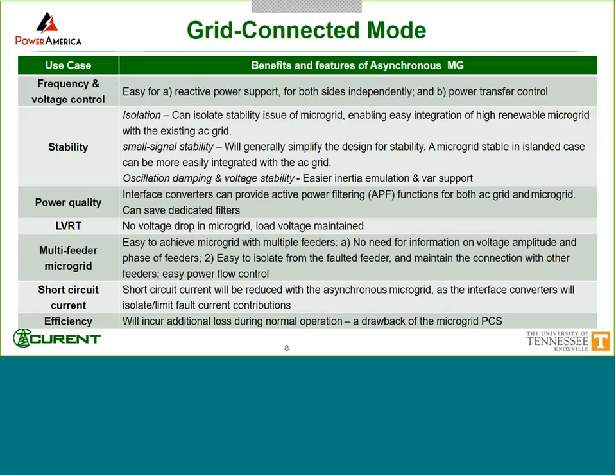And power quality: this interface PCS converter can actually provide filtering, which will be explained a little bit later, and that can help save some additional filters you may need in the case of nonlinear loads. And low voltage ride-through I already showed. Another benefit is it's easy to connect to a microgrid with multiple feeders. And the short circuit current may or may not be a benefit, because with these converters there, the short circuit current will be defined by the converters rather than by the loads. Of course, adding this link in between will cause additional loss during normal operation, so that is something we have to take care of.